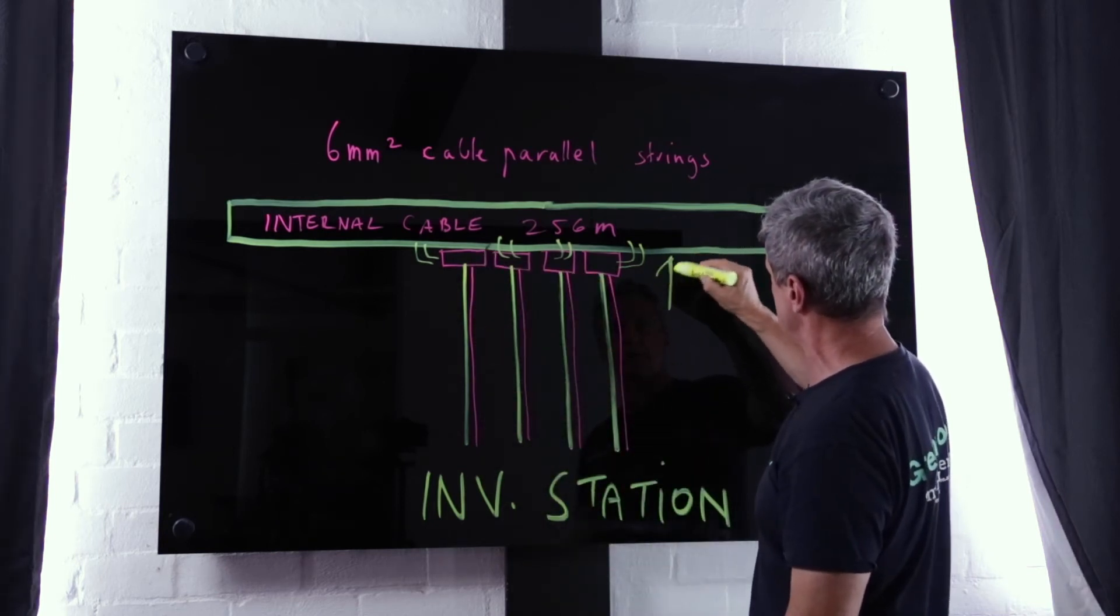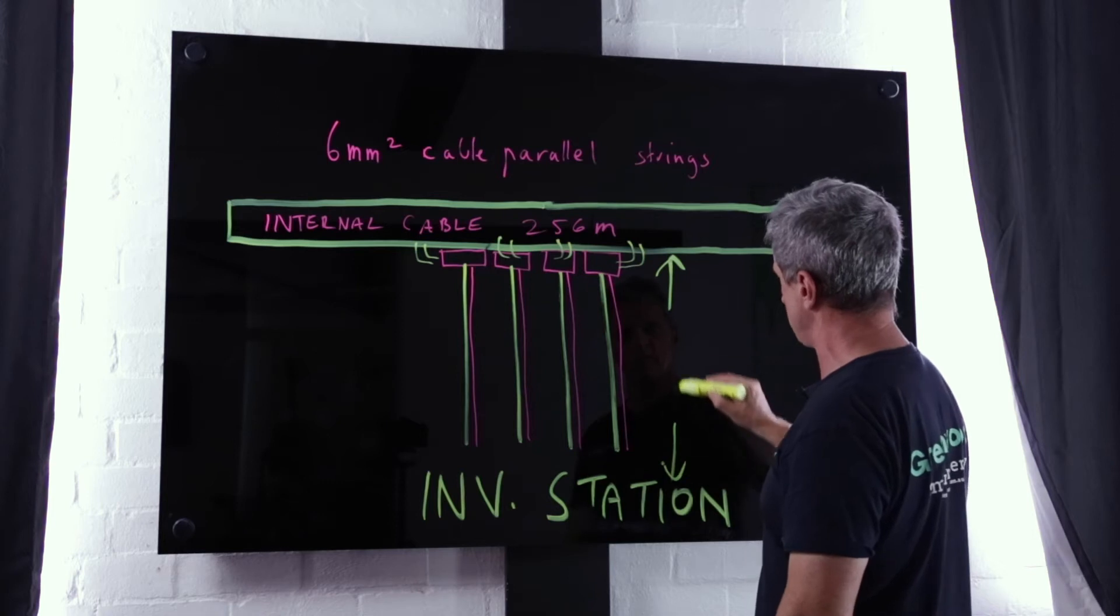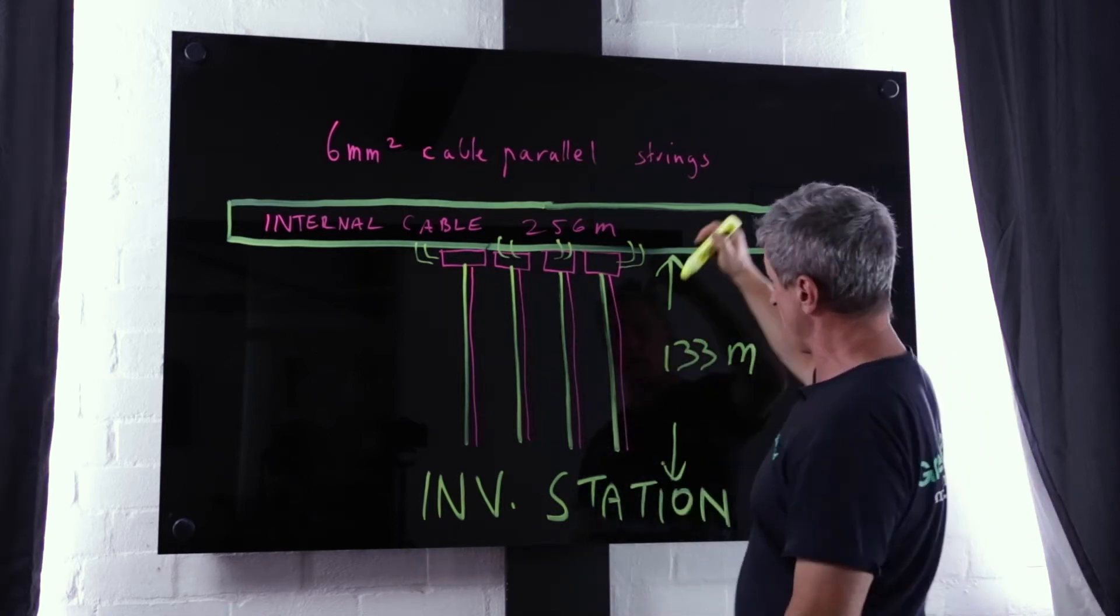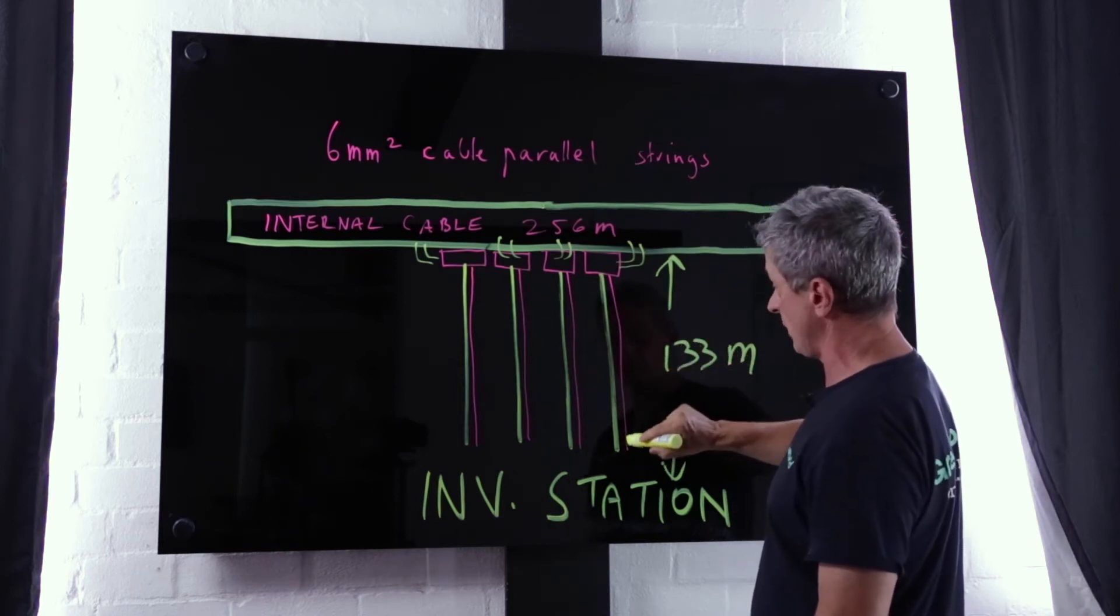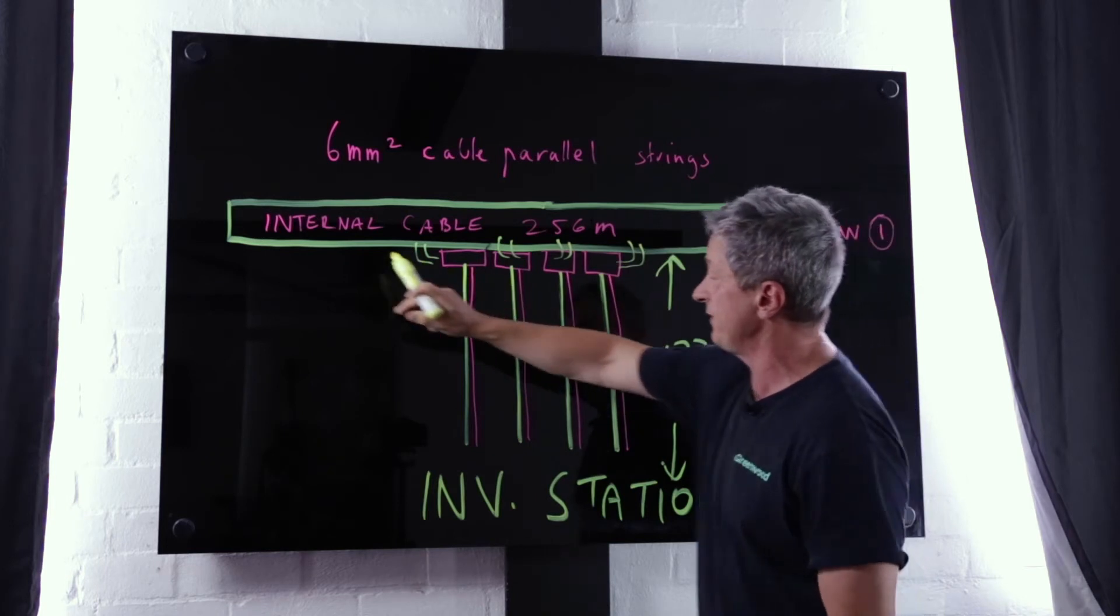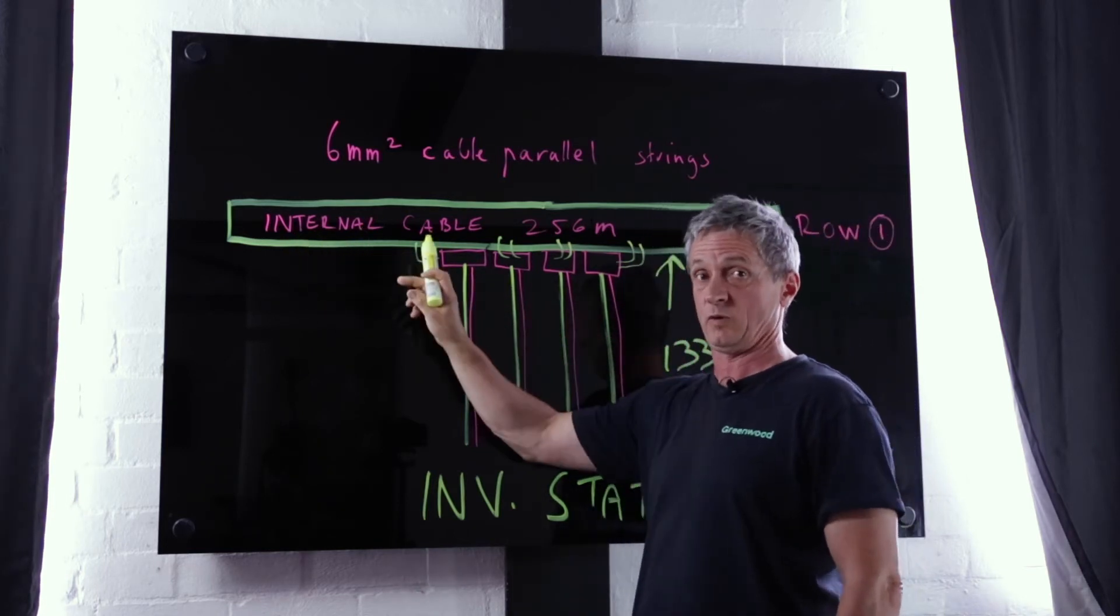So we're doing our volt drop calculations first on this run and then on the internal runs as well. Now in the 4mm calculation we went worst case scenario, the string that's furthest away from the centre was 166 meters of cable that run from there all the way through.